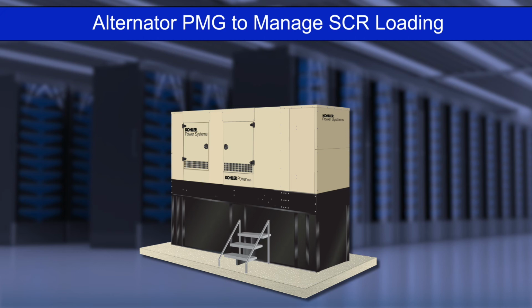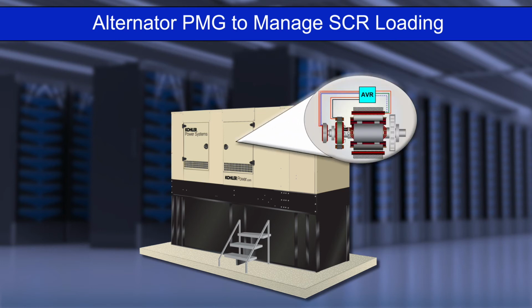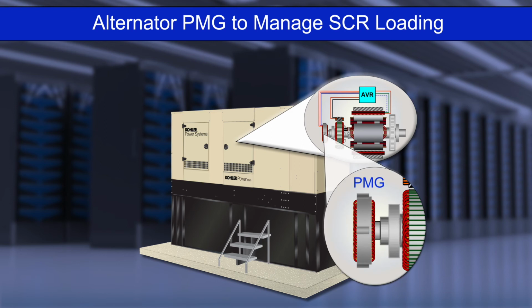Silicon-controlled rectifiers, SCRs, within UPS systems can produce harmonic distortion to an AC power curve. For applications such as data centers, your generator supplier will recommend an upgraded AVR voltage controller to manage a high percentage of SCR loads. Alternators fitted with PMG permanent magnet generator excitation mitigate any adverse SCR load characteristics.